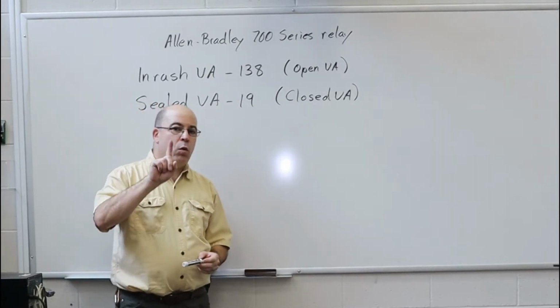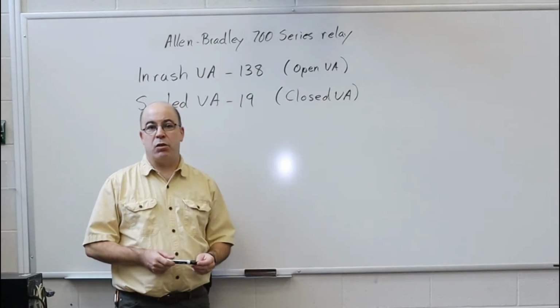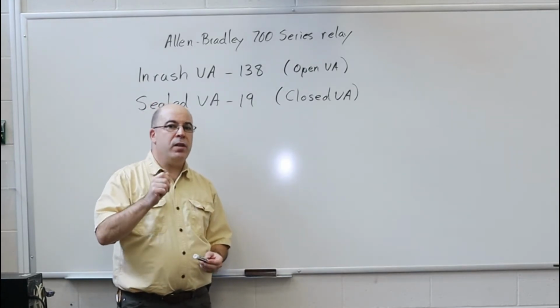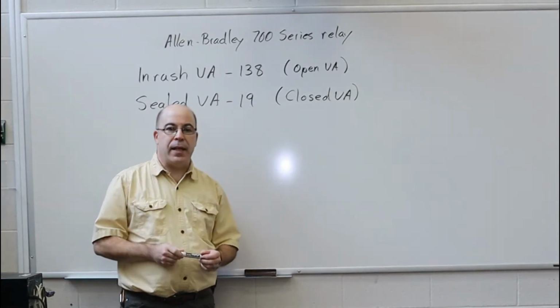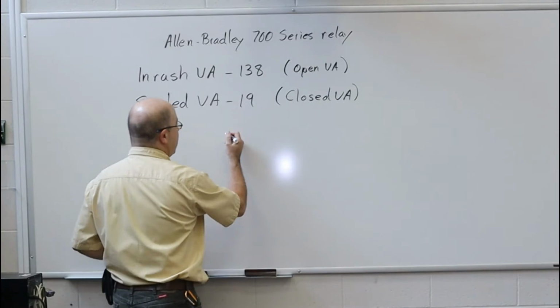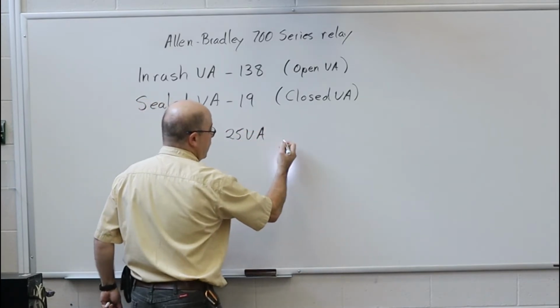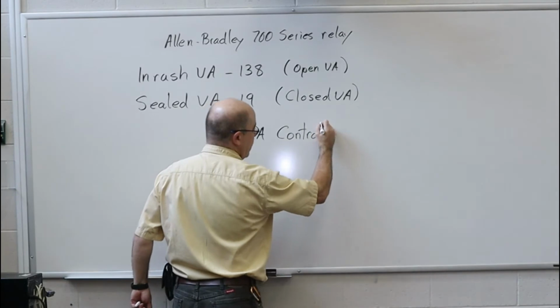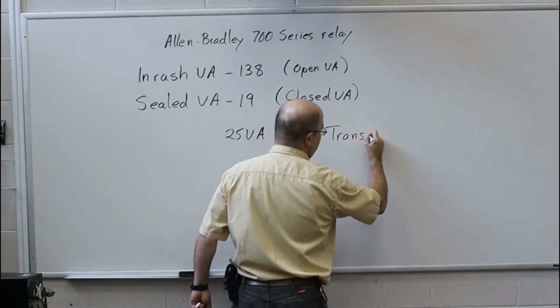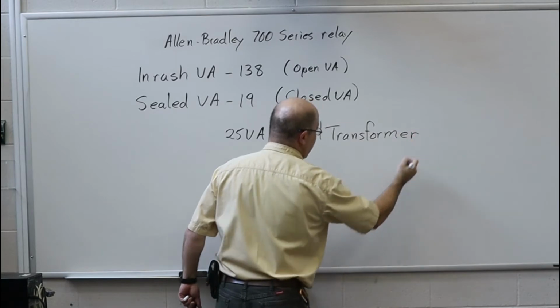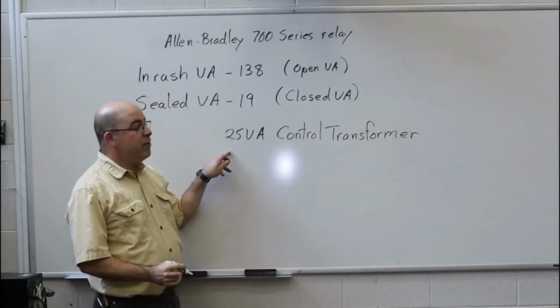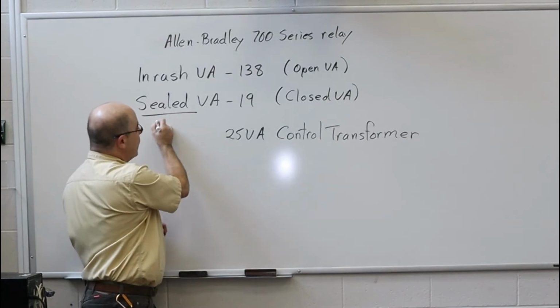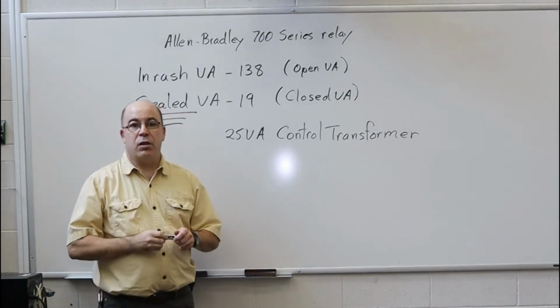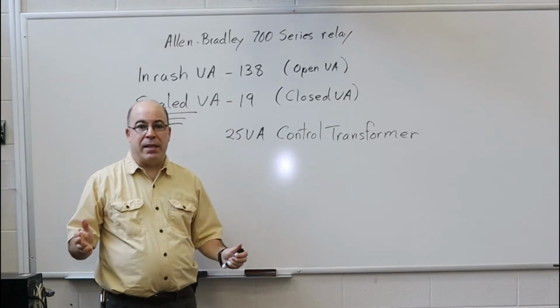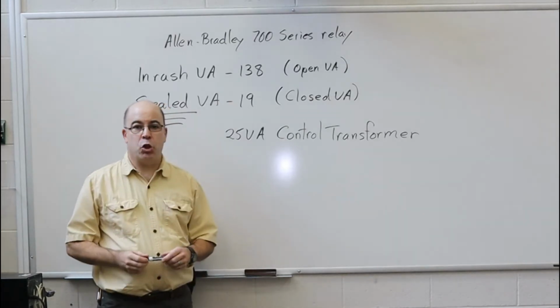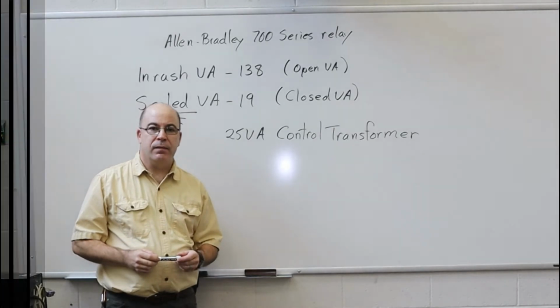Now, when we start talking about 125 VA control transformer, I have more than enough power to energize one of these relays. But accordingly, at 25 VA for a control transformer, I will not have enough power to have more than one control relay closed at any point in time. So that's what the math is showing us. Let's put that to the test.